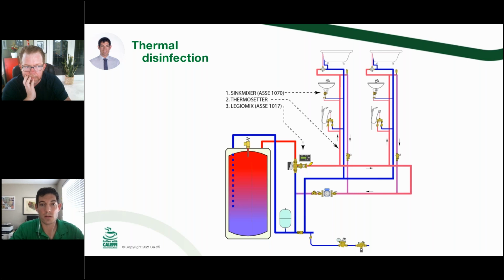So what you can do with the LegioMix is program what that return sensor is going to see. You say, you need this to get up to 140 and you need to maintain that for 32 minutes. Then we're going to consider that disinfection cycle complete. You could up the supply temperature and reduce the amount of time that you need to see that.